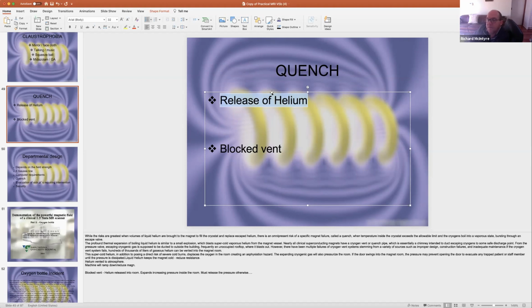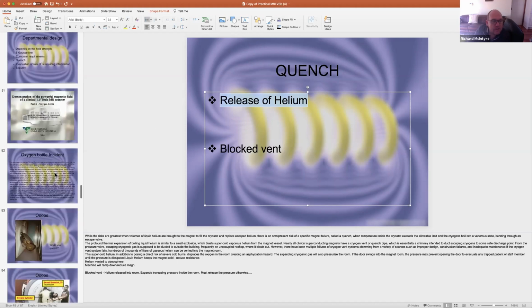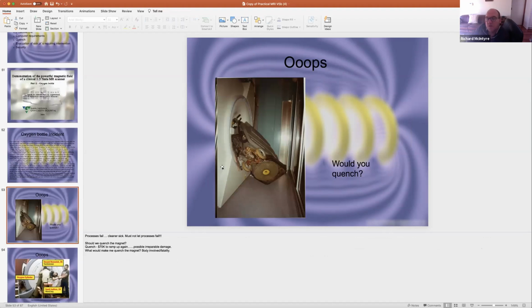But if there's an earthquake or something that happens to block that vent, that gas can come in the room and cause a lot of pressure inside the room. It's happened only a handful of times in the world. As I said, usually the liquid helium turns to gas, it goes through the quench pipe and out into the atmosphere. The machine ramps down, so we go from 3 Tesla to practically 0 in 10 seconds, and we get the patient out. The only reason we would quench this machine is in a medical emergency.